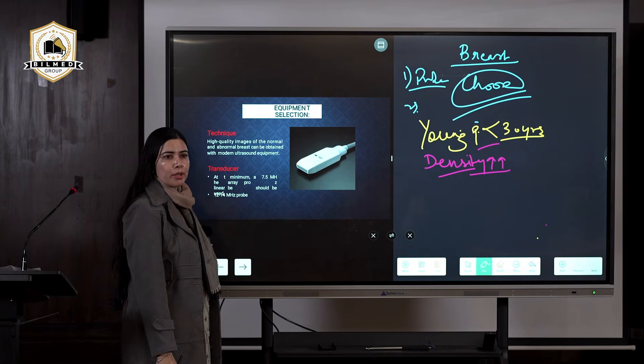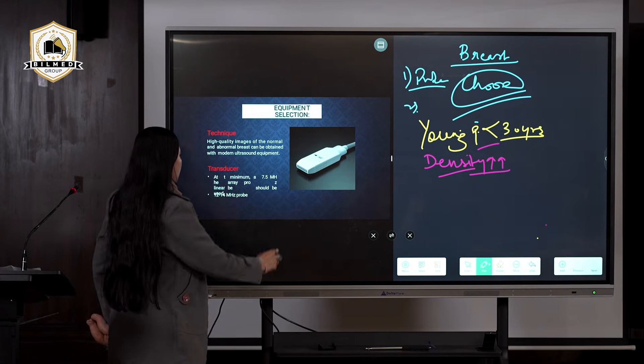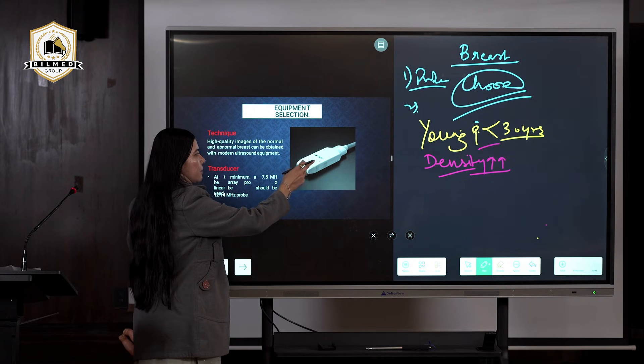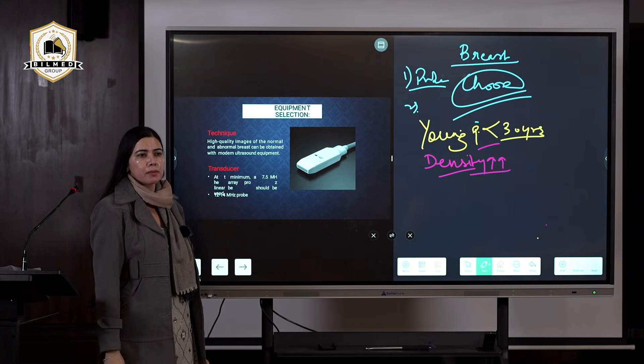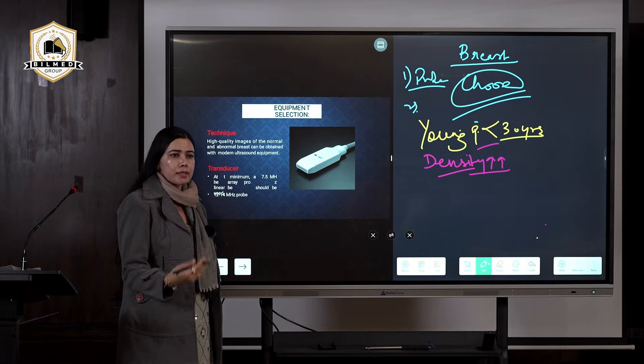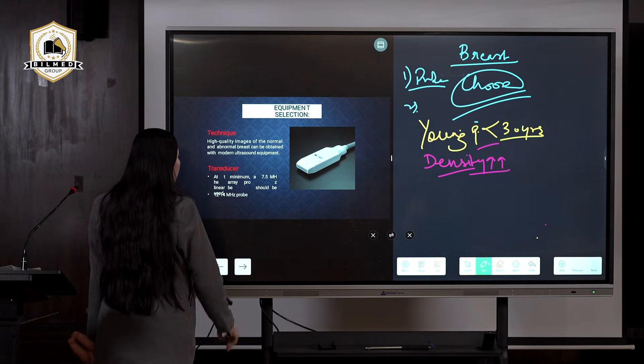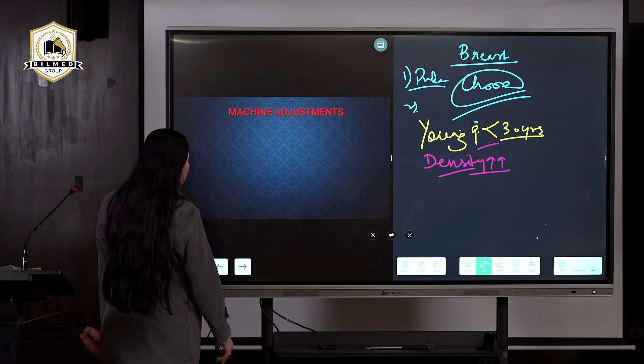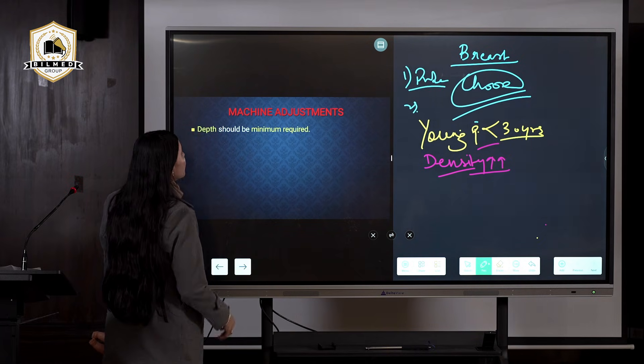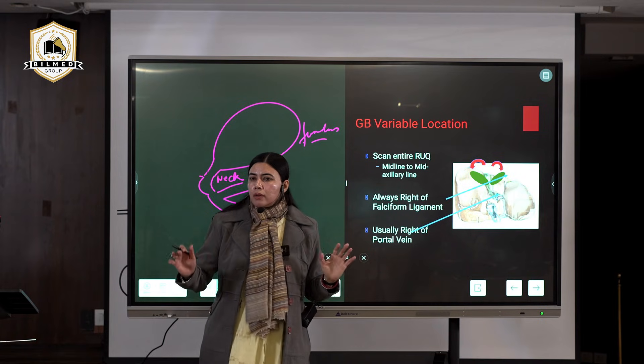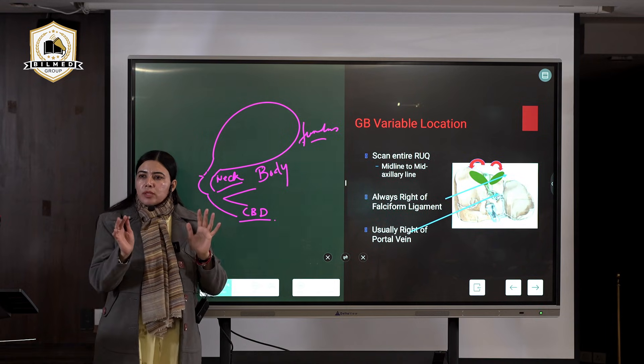This is the linear probe that I told you, the high frequency probe. Frequency below 7.5 megahertz is not acceptable because we want to scan this superficial organ, so we are not going to choose lower frequency.